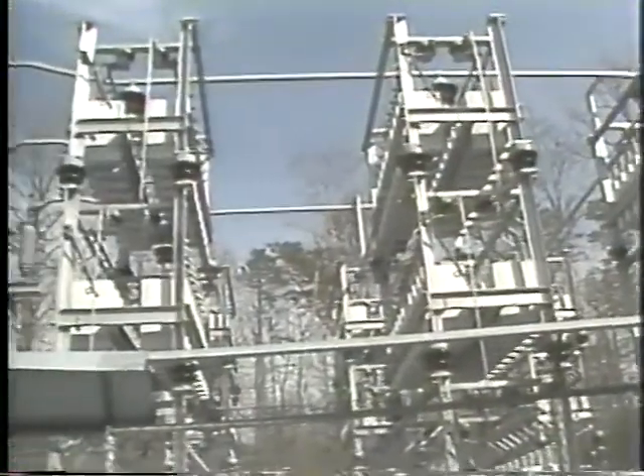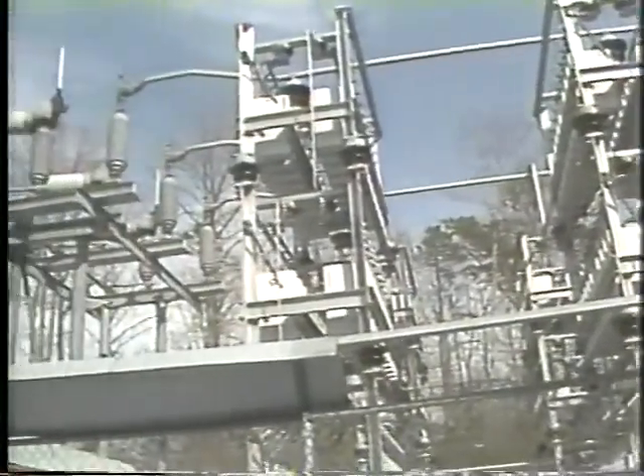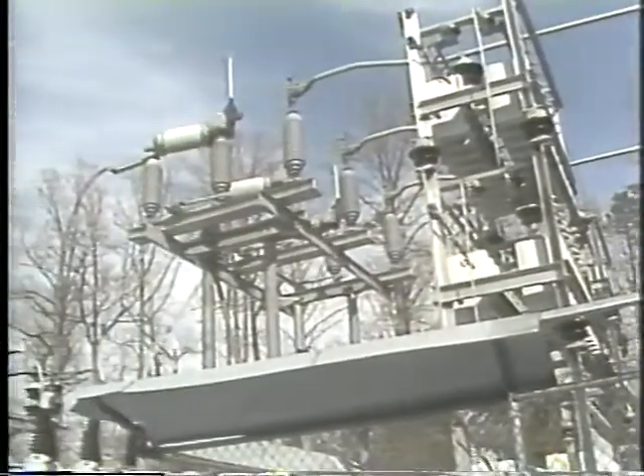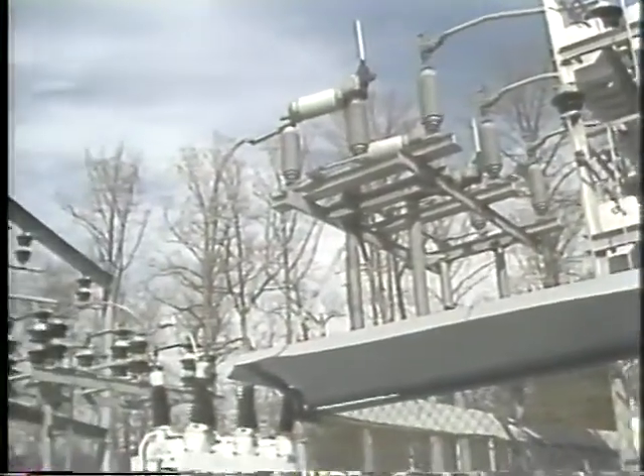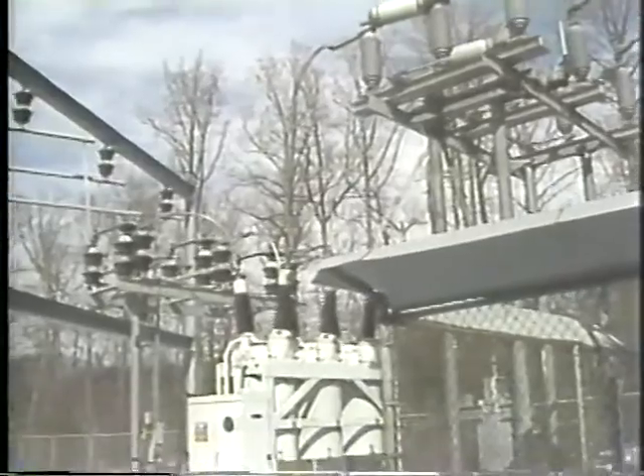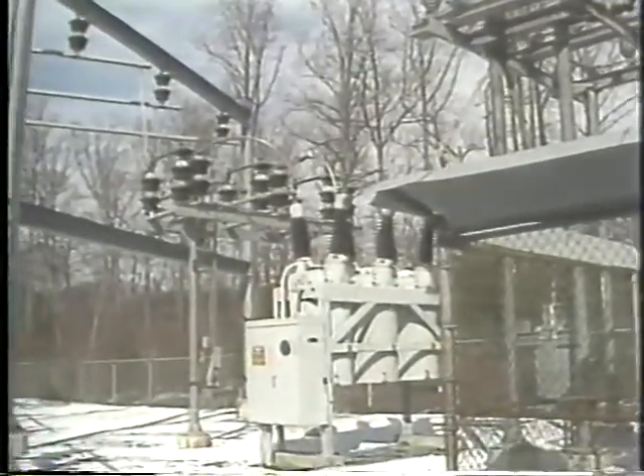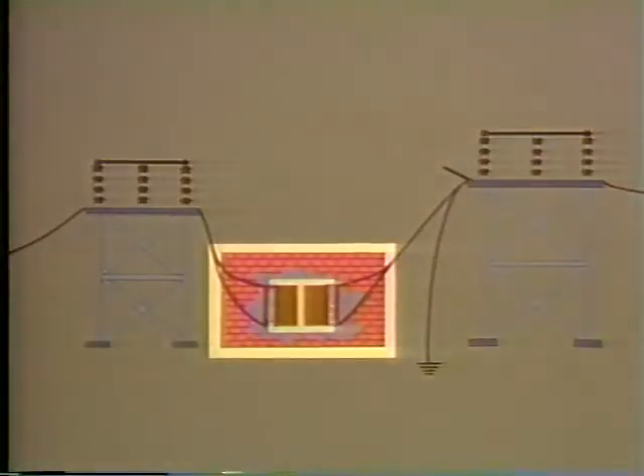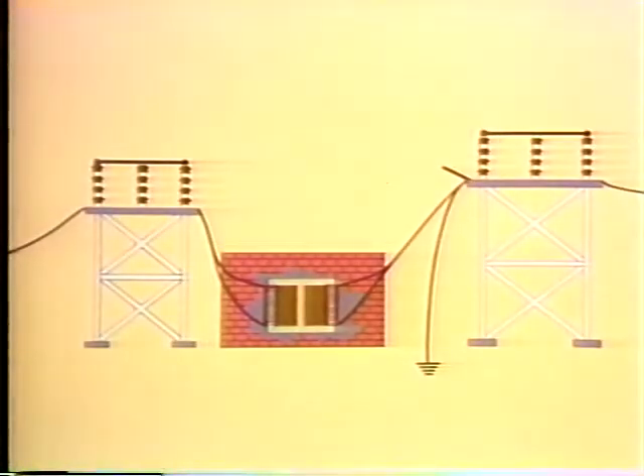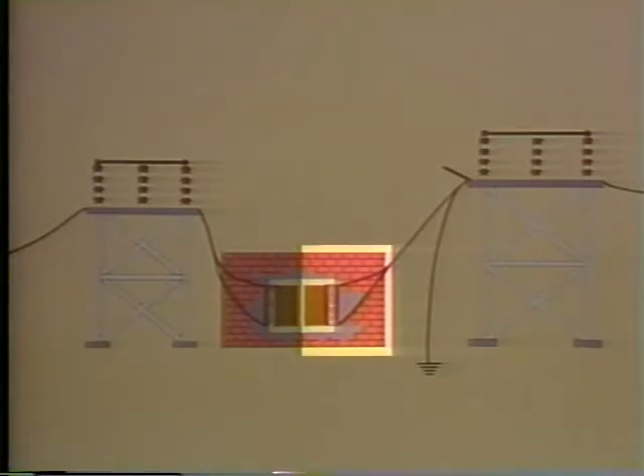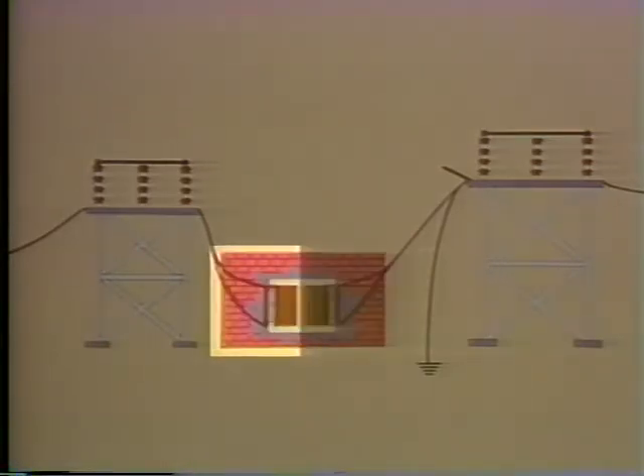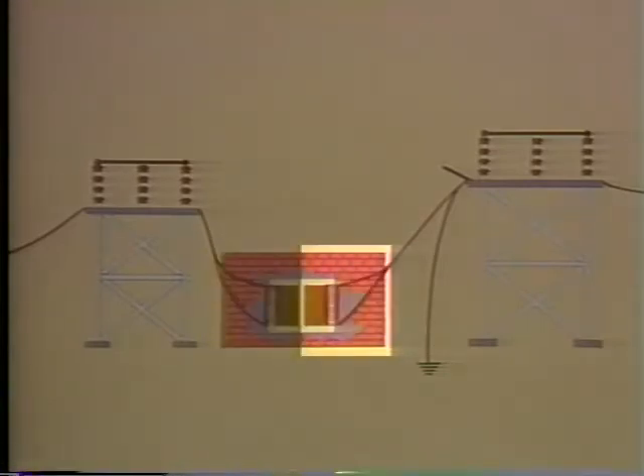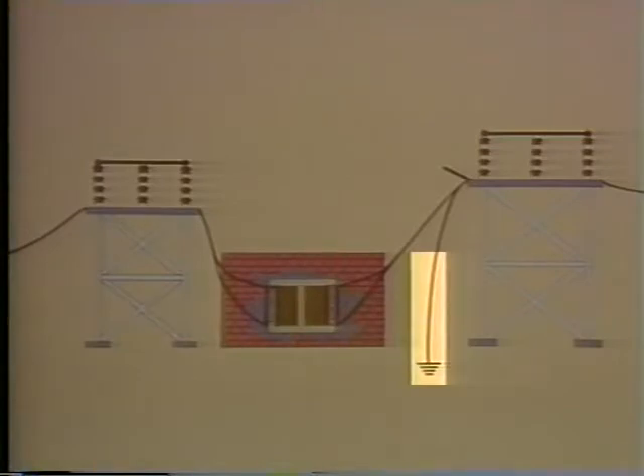Many types of high voltage equipment are designed with special arrangements for safety grounding. We're going to see two different examples of isolating and grounding equipment for maintenance. This transformer is our first example. An electrician's going to prepare for work on the 230 kV primary side of the unit. The transformer has to be unloaded on the secondary side and de-energized on the primary side. Then the primary has to be grounded.